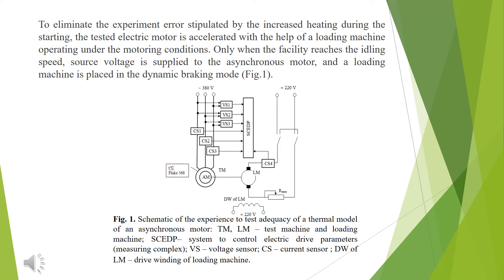To eliminate the experiment error caused by increased heating during starting and braking, the tested electric motor is accelerated with the help of a loading machine operating under motoring conditions. Only when the facility reaches idling speed is source voltage supplied to the asynchronous motor, and the loading machine is placed in dynamic braking mode. Figure 1 shows the schematic of the experiment used to test the adequacy of the thermal model of an asynchronous motor.